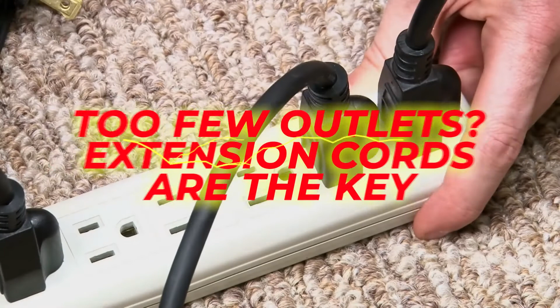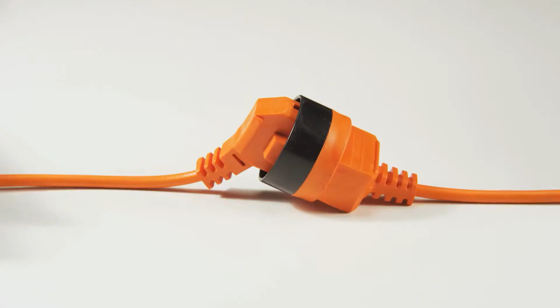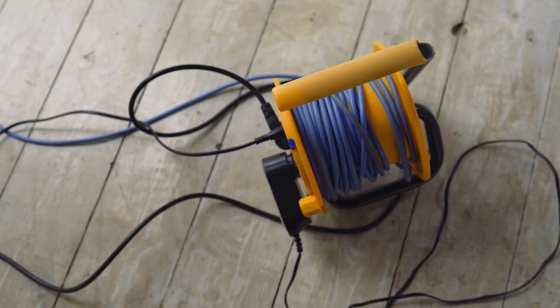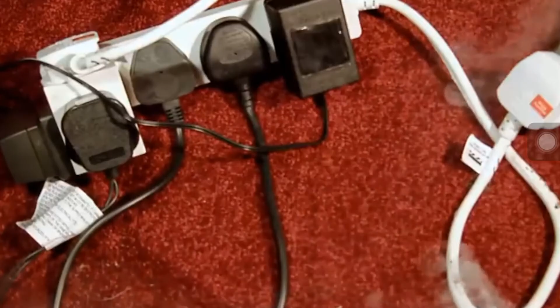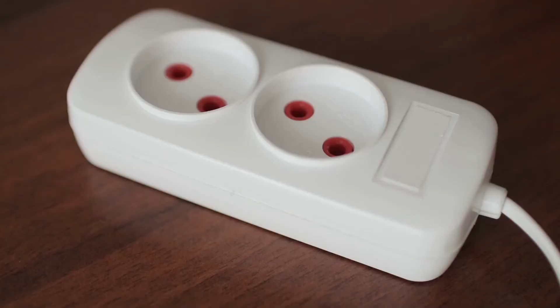Too few outlets? Extension cords are the key. Last but not least, far too many places suffer from a lack of outlets in the plan. The solution? Heavy reliance on extension cords and power strips. Although there's no code violation for this, it still poses a danger if used heavily, especially on cheap or bargain extension cords. Undersized extension cords, 16 gauge or smaller, can overheat and ignite a fire if loads are too heavy.